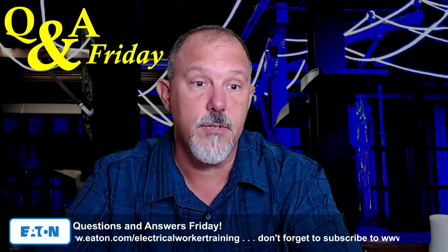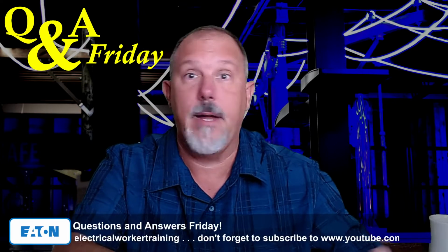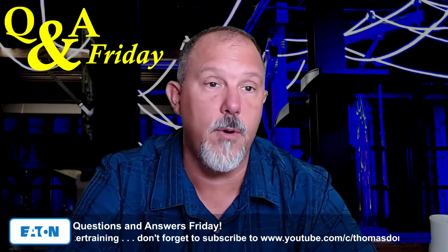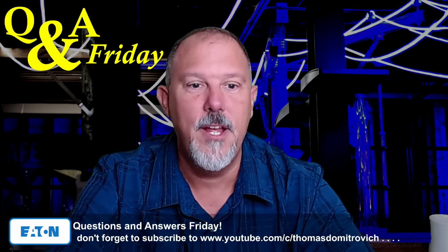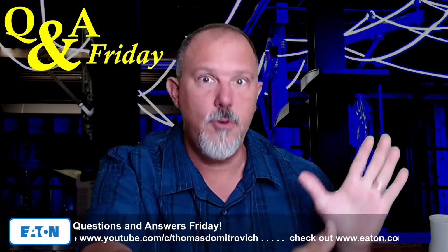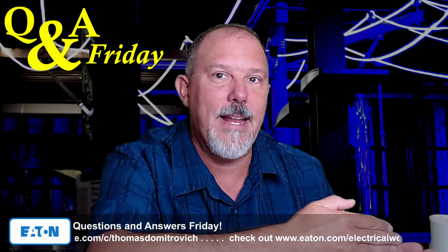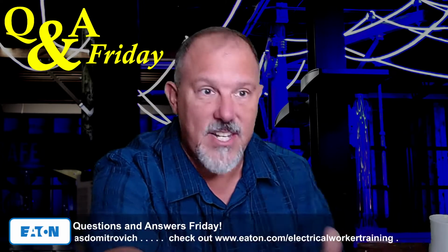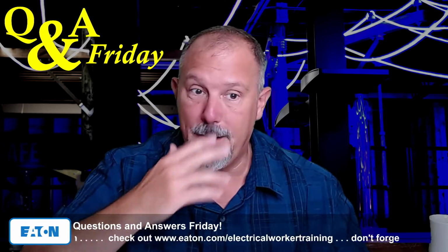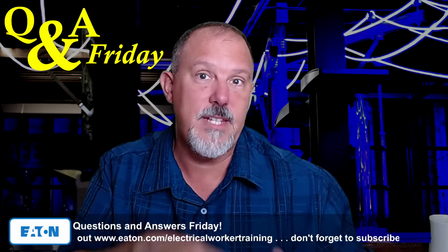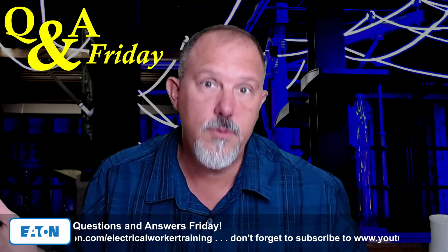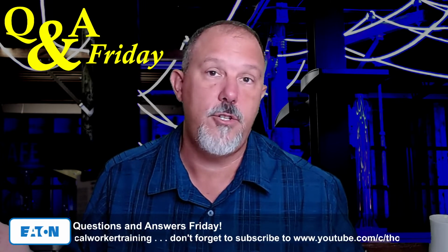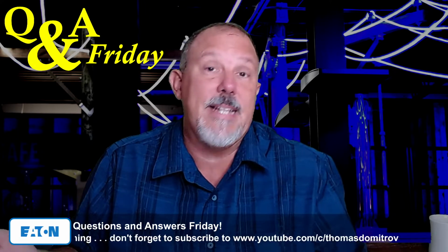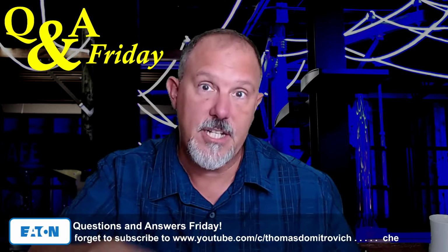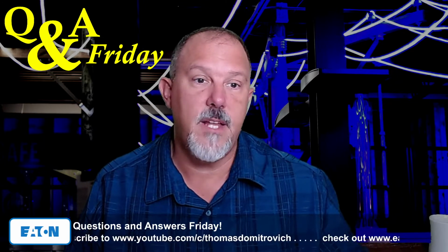There are some manufacturers. Now, you may have one manufacturer, and I could tell you there's probably at least one manufacturer I'm aware of where I could say all of their VFDs don't, and not because of high frequency, because they are using the equipment grounding conductor as a load return. They're actually putting a load between hot and ground because there's no neutral there. It's a 60 hertz thing. And there's nothing in the UL standards to say you can't use that equipment grounding conductor as a neutral for a neutral load. There's no test in there for it. And they're trying to change that right now. So I would say it has nothing to do with the VFD.